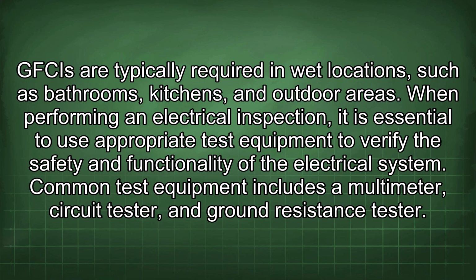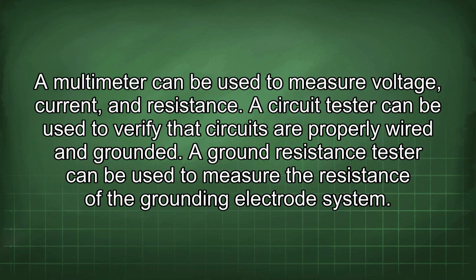When performing an electrical inspection, it is essential to use appropriate test equipment to verify the safety and functionality of the electrical system. Common test equipment includes a multimeter, circuit tester, and ground resistance tester. A multimeter can be used to measure voltage, current, and resistance. A circuit tester can be used to verify that circuits are properly wired and grounded. A ground resistance tester can be used to measure the resistance of the grounding electrode system.